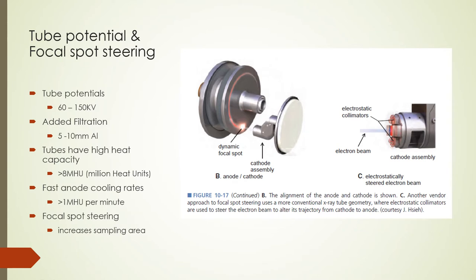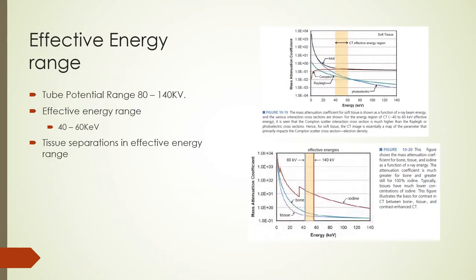Newer CT tubes have high heat capacities greater than 8 million heat units and up to 30 million heat units in some cases, with fast anode cooling rates of more than 1 million heat units per minute. In some tubes, the X-ray beam is steered to hit different portions of the anode to reconstruct more scan planes by increasing the sampling area. While CT tubes may operate in the 80 to 140 kV range, useful effective energies lie in the 40 to 60 keV range.